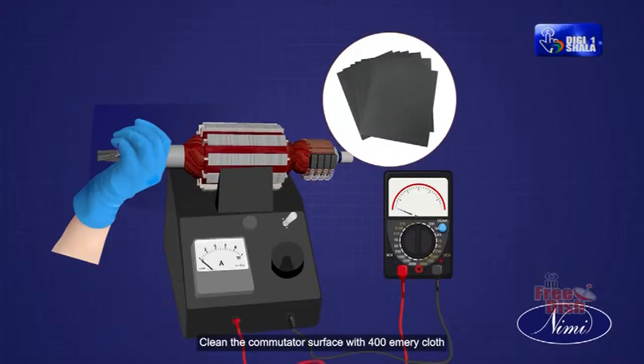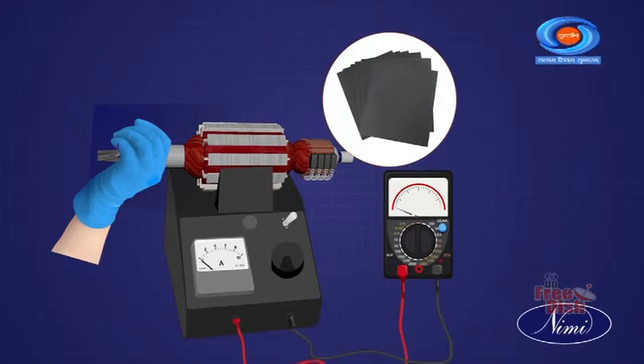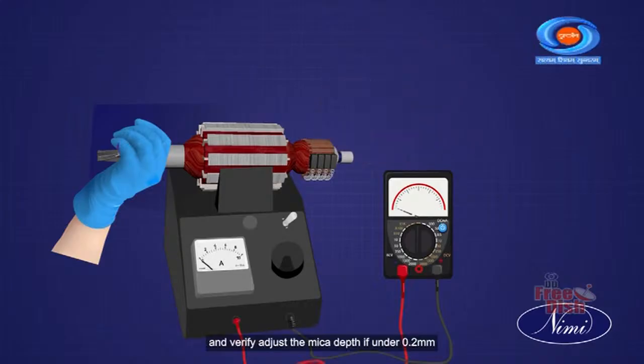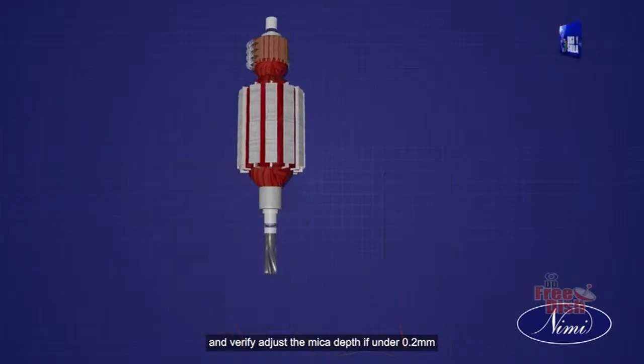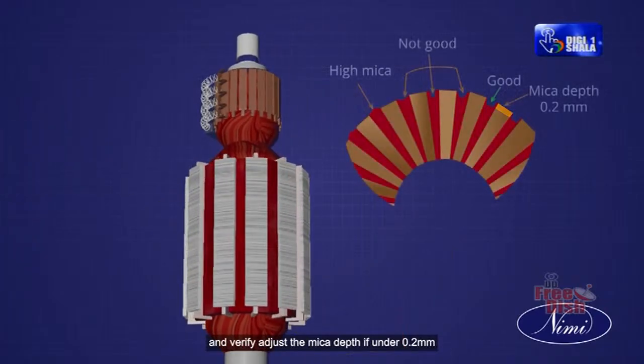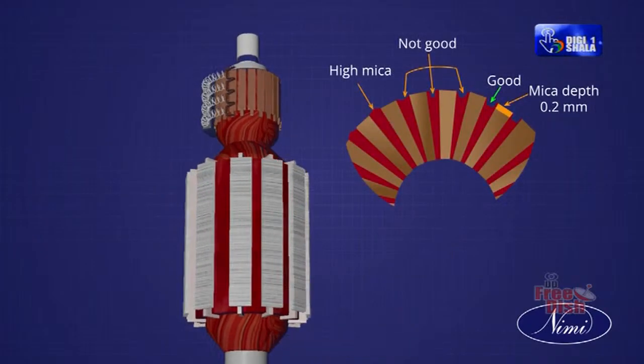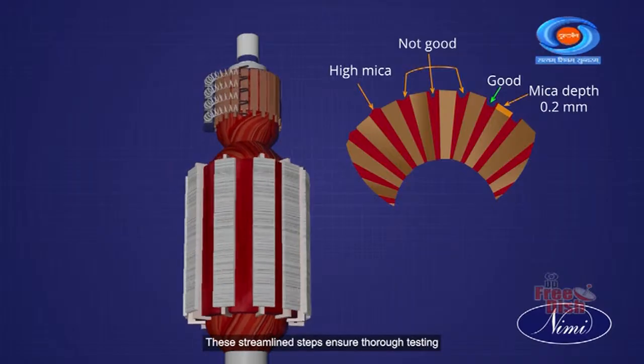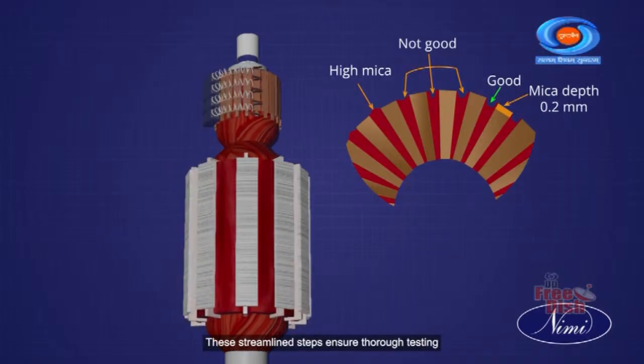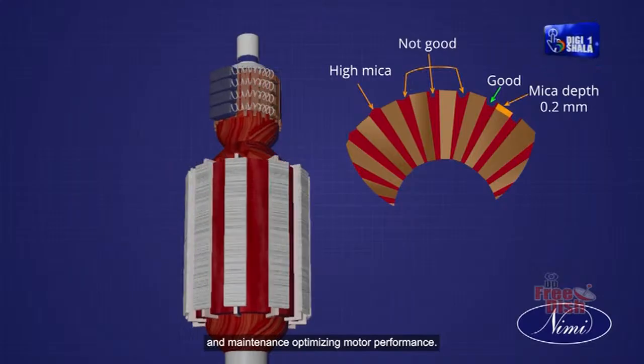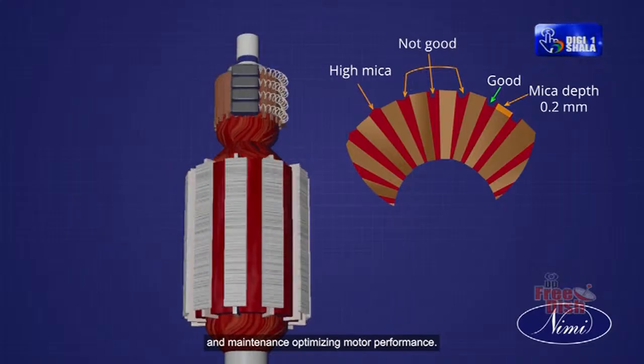Clean the commutator surface with 400 emery cloth and adjust the mica depth if under 0.2 mm. These streamlined steps ensure thorough testing and maintenance, optimizing motor performance.